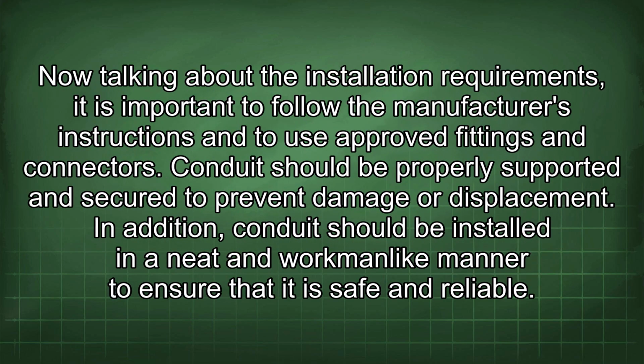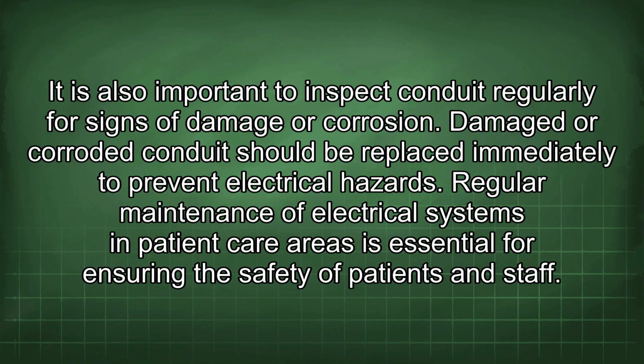Now talking about the installation requirements, it is important to follow the manufacturer's instructions and to use approved fittings and connectors. Conduit should be properly supported and secured to prevent damage or displacement. In addition, conduit should be installed in a neat and workmanlike manner to ensure that it is safe and reliable. It is also important to inspect conduit regularly for signs of damage or corrosion. Damaged or corroded conduit should be replaced immediately to prevent electrical hazards.